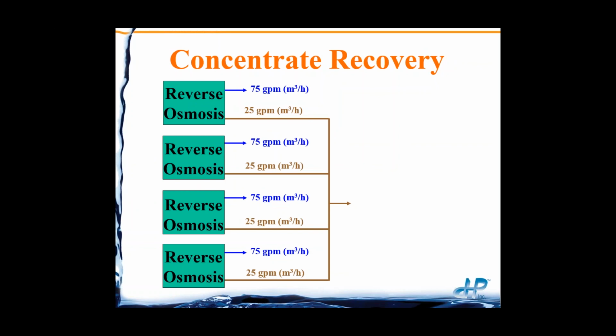Let's say you have a 15-year-old plant, 20-year-old plant. You've had reverse osmosis in it for 10 or 20 years, or maybe from startup. And the most common off-the-shelf, cheapest RO units are typically 75% recovery for brackish water.